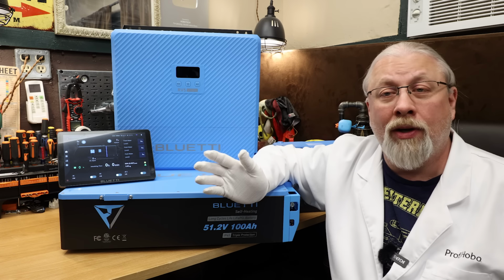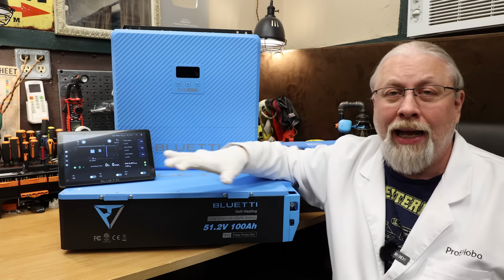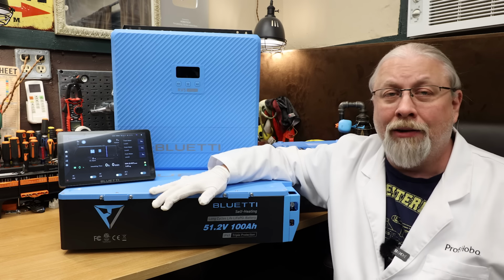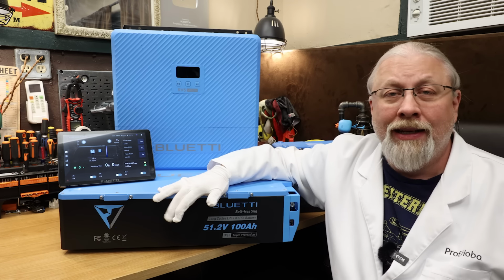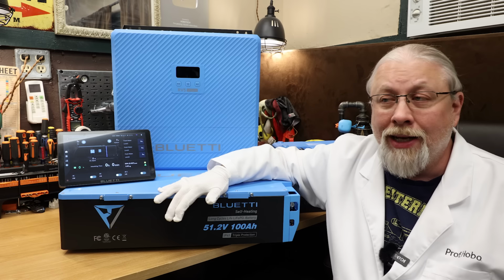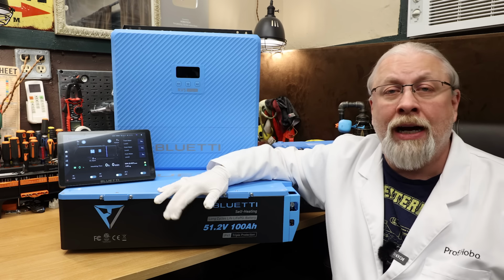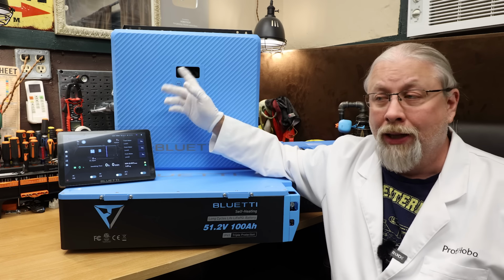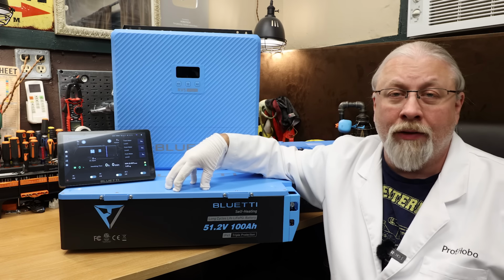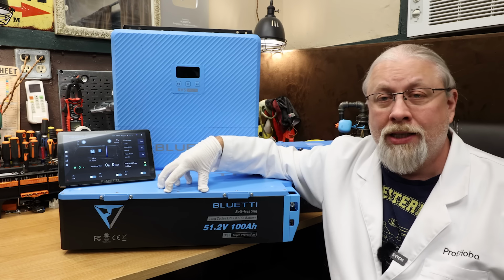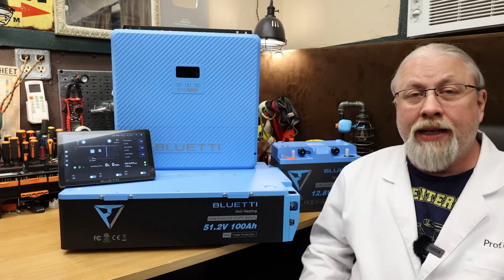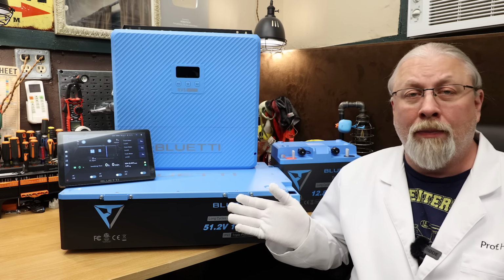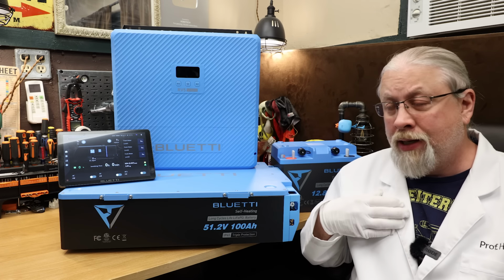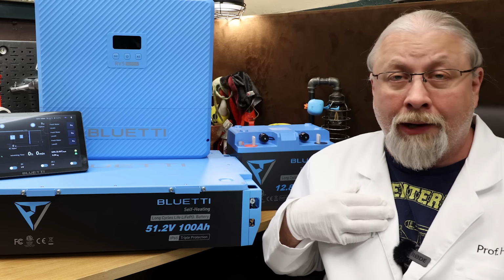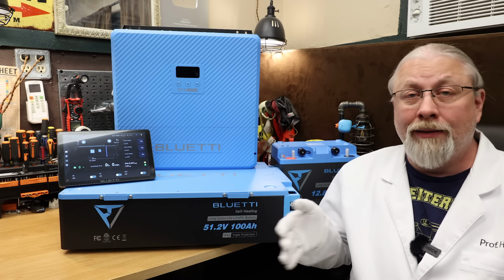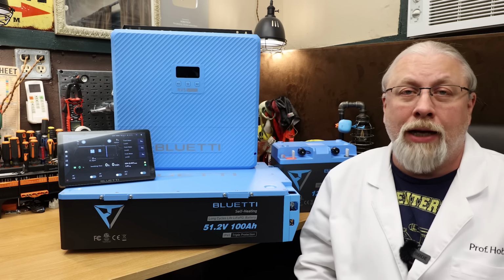And that's on top of the price of the kit itself. Besides the solar limits, I was kind of miffed when I only got 88.5 amp hours out of this battery. The first time I tested it, it completely shut down at the end. The second time it didn't. However, the RV5 screen said 0% and wouldn't let me turn anything on, while there was still juice left in the battery, it was inaccessible, so it just may as well not exist. Seeing how every other 48 volt 100 amp hour battery on the market I've tested meets or exceeds 100 amp hours, I'm crying foul. Maybe I have a bad battery. Maybe Mercury was in retrograde during testing.